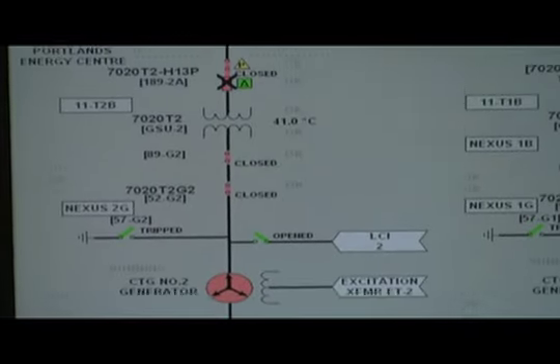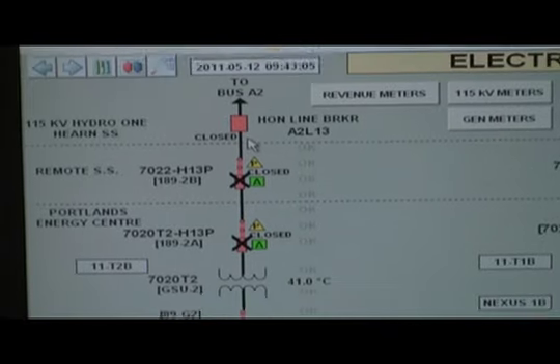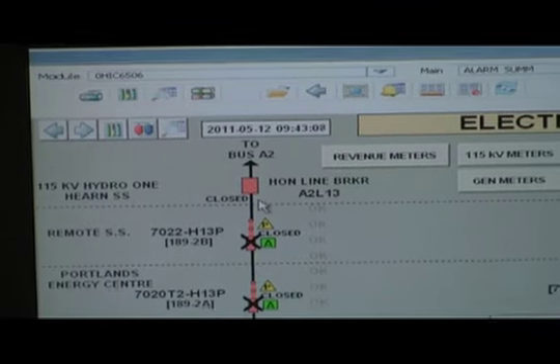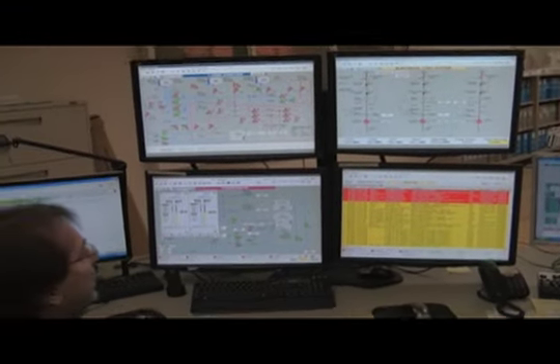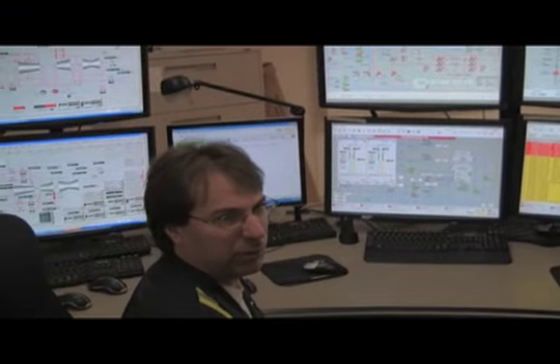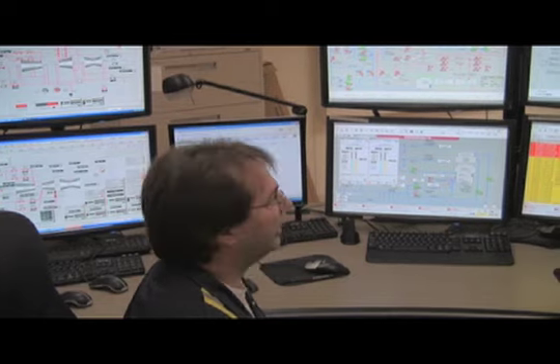And is the system operator monitoring this now, or do you have to report it to them on a regular basis? Well, they communicate to us through this machine here. They'll send us dispatches, as frequently as within 5 minutes, and they'll let us know what plant load to go to. And you can get to that within how much time? Well, they're in 5-minute intervals, so they expect us to reach it within the 5 minutes. Within 5 minutes? Yeah.